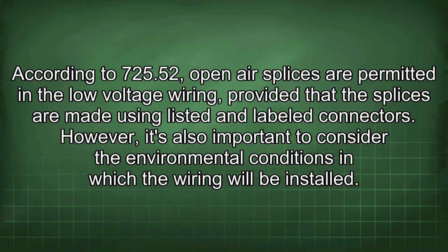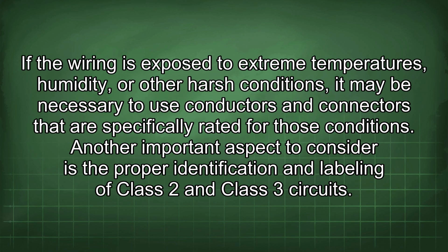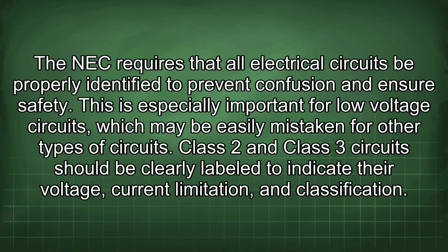However, it's also important to consider the environmental conditions in which the wiring will be installed. If the wiring is exposed to extreme temperatures, humidity, or other harsh conditions, it may be necessary to use conductors and connectors that are specifically rated for those conditions. Another important aspect to consider is the proper identification and labeling of Class 2 and Class 3 circuits. The NEC requires that all electrical circuits be properly identified to prevent confusion and ensure safety. This is especially important for low-voltage circuits, which may be easily mistaken for other types of circuits. Class 2 and Class 3 circuits should be clearly labeled to indicate their voltage, current limitation, and classification.